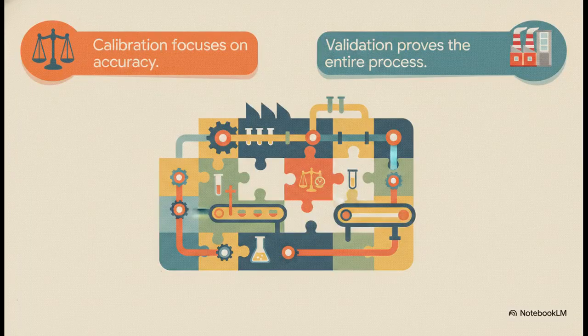Now, what's really interesting about this slide is how these two concepts interact, because people actually mix them up all the time. But as the presentation makes crystal clear, calibration is actually a crucial puzzle piece inside the larger picture of validation. Calibration focuses solely on the accuracy of one single instrument. Validation is the whole overarching umbrella. It focuses on the entire process consistently producing the quality we expect. You simply cannot have a validated process if your instruments aren't calibrated.